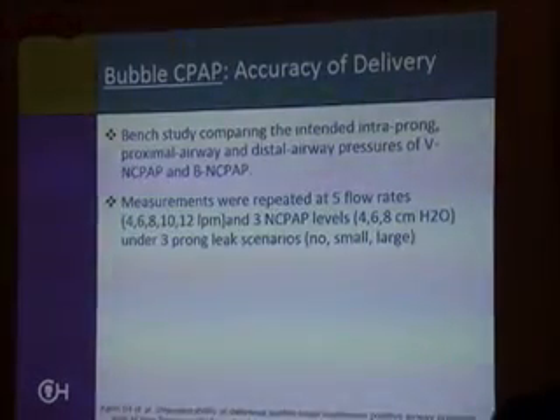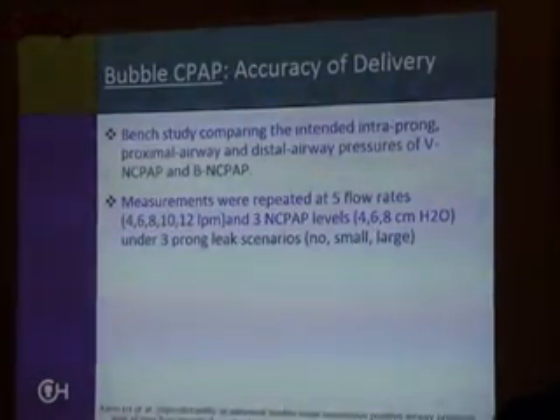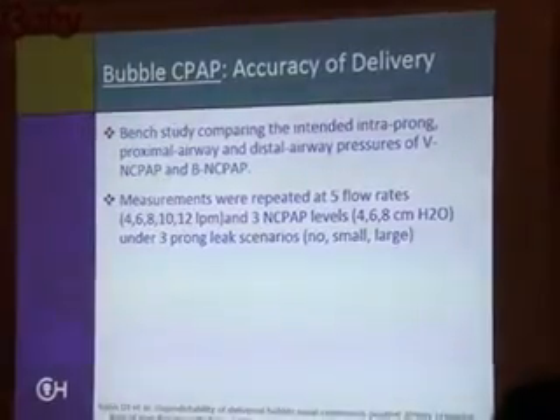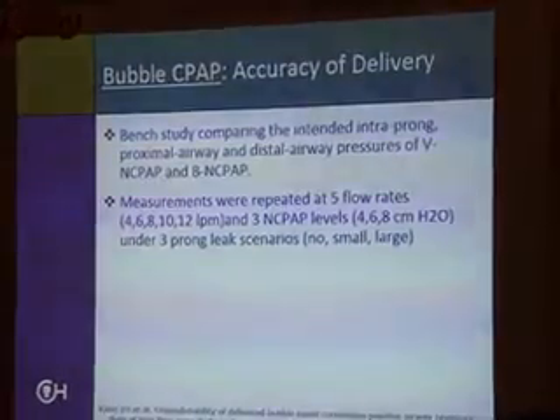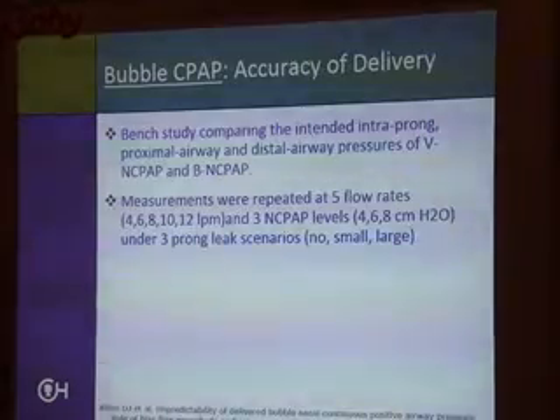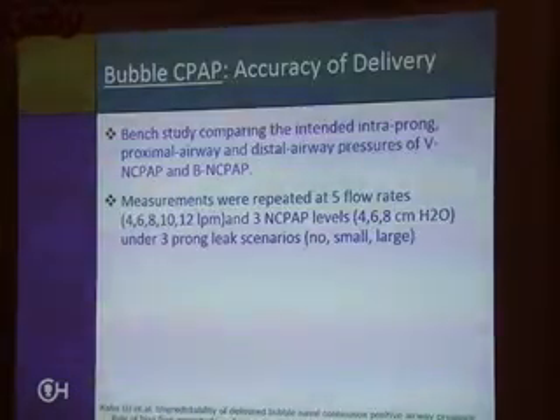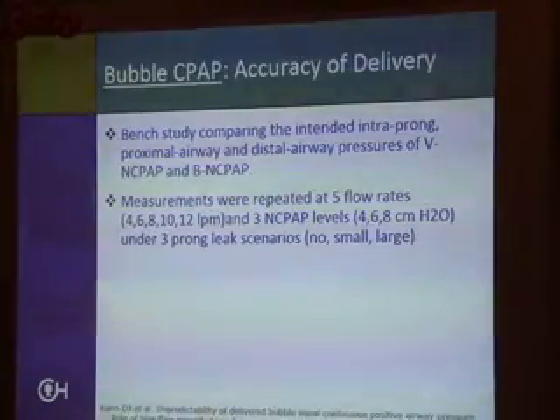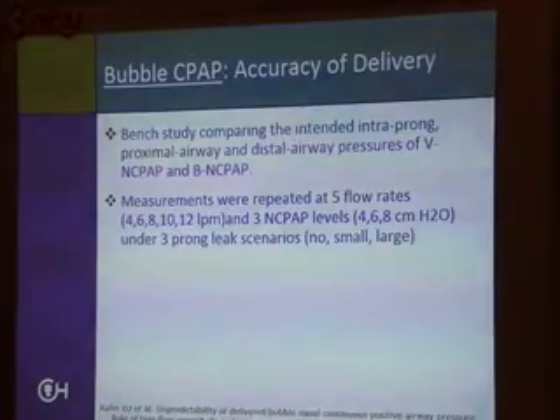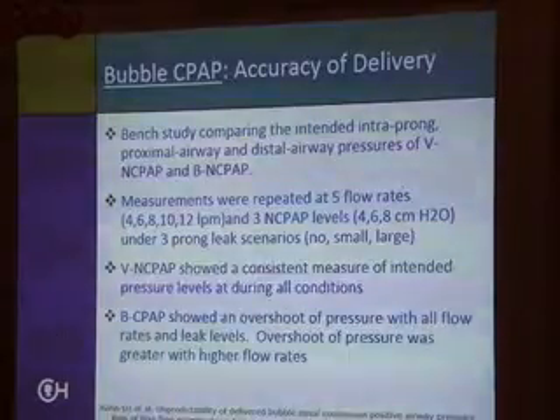So our next study looking at accuracy of delivery was another bench study that also looked at the intended intra-prong pressure, proximal airway pressure, and distal airway pressures, comparing ventilator-driven CPAP versus bubble CPAP. So now we're comparing the two different types that are all continuous flow. The measurements were repeated at 5 different flow rates, 4, 6, 8, 10, and 12, and at 3 different CPAP levels. They looked at 4, 6, and 8 at all those different flow measurements. And under the 3 conditions of no leak, small leak, or large leak. And this was published in 2007 in Pediatric Research Journal.